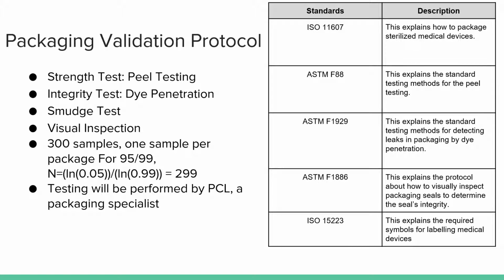In order to validate the packaging, several tests will be performed, and the standards are listed on the right side of the slide. For our strength test, we chose peel testing, and for our integrity test, we chose a dye penetration test. Smudge testing will also be done to ensure that the label does not smudge, and visual inspection will be done in order to test the smudge testing in addition to any other potential flaws of the packaging.